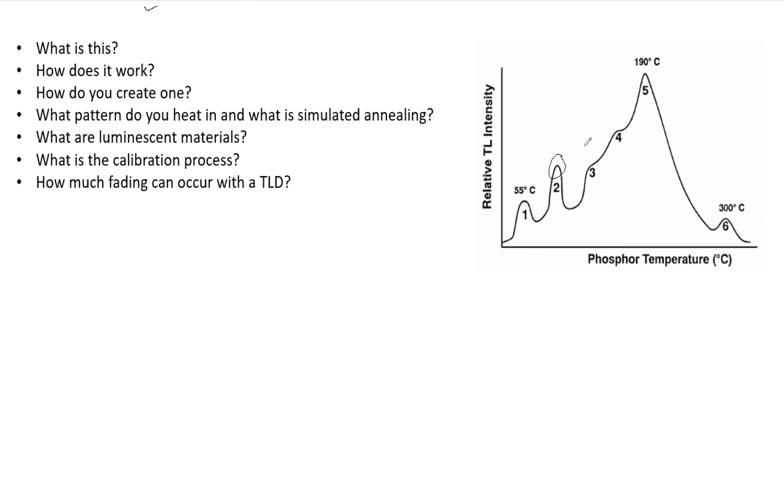It's important to understand not just that this is a glow curve, but how that works and be able to verbally explain it. So now, how do you create one? The first step is you have to preheat the TLD. You can look online, there are different temperatures and ranges and times, but you want to preheat the TLD. Then in its acquisition, you want to use a constant heat rate, and finally use annealing to reset the TLD.